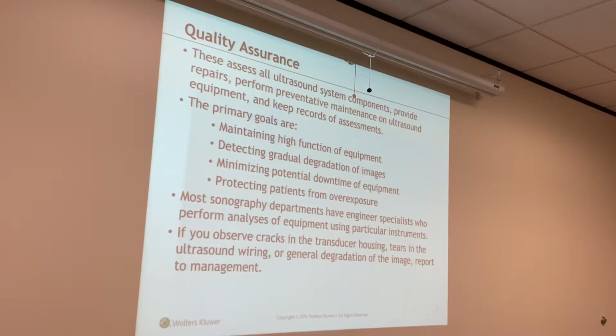When you examine, all of our machines here in the lab are at 100% power because they're all donations and they were taken out of circulation for various reasons. So all of them are at 100%. So I'm not going to sit there and talk to you with the transducer live because it's just sending heat waves, sound waves down into your body in one place. Because we sit there and we talk for 15 minutes, okay? Well, if you're going to talk, just hit the freeze button. Just hitting the freeze button will make your transducer not active, okay?